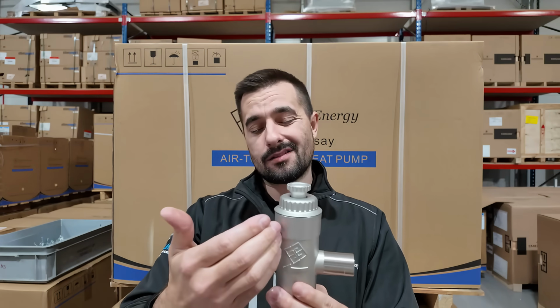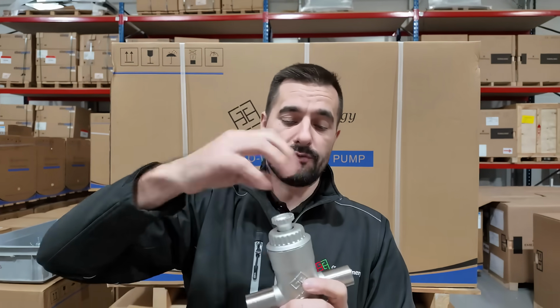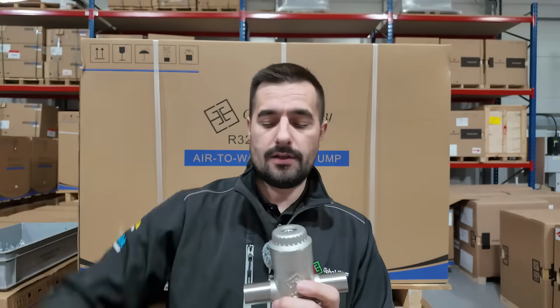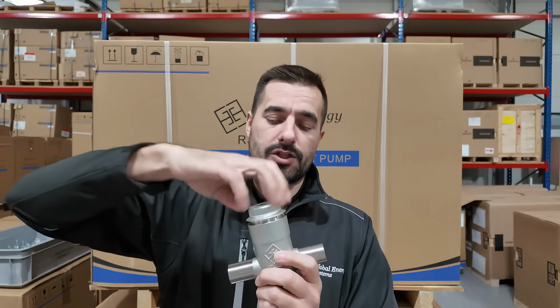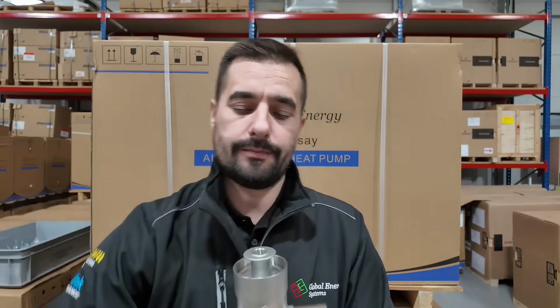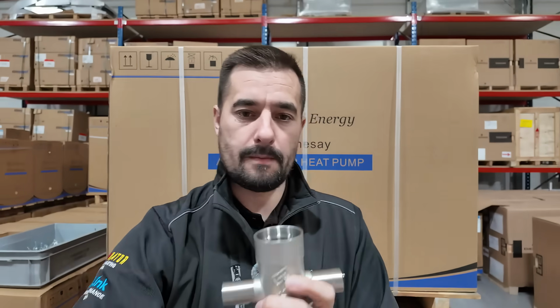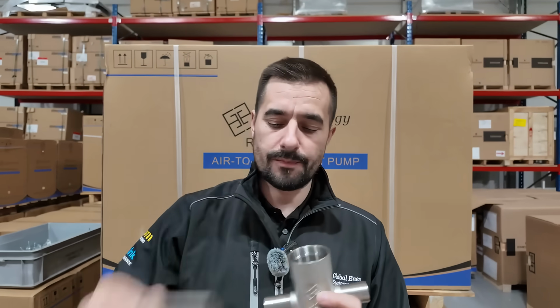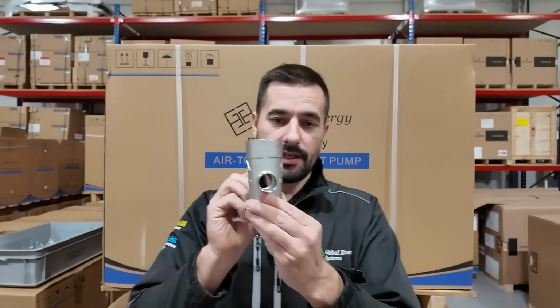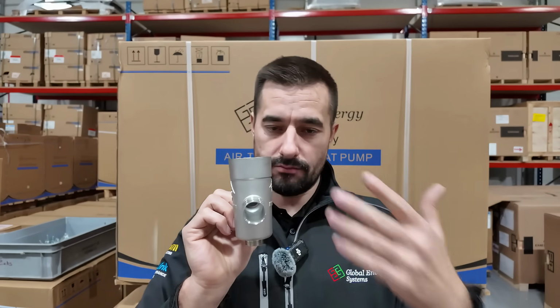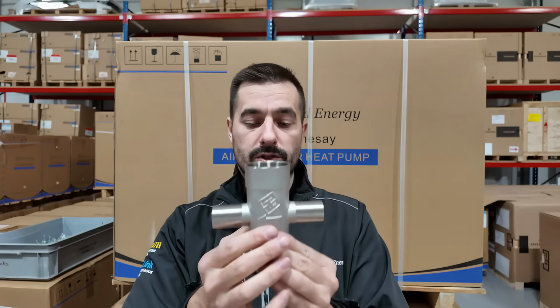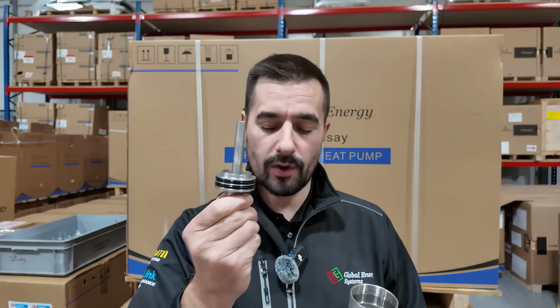So we made this filter, and it is Global Energy branded. And what does it do? So it's got a gauze in it and it's got a magnet. If we remove the magnet and move the central section, I'll show you inside. Got a gauze. So what's good about it? Good thing is it's got a really good high Kv value. We can chuck loads of water through it and the pressure doesn't build up too much. The other thing is the big gauze takes forever to block up and the magnet itself pulls away the metallic waste.